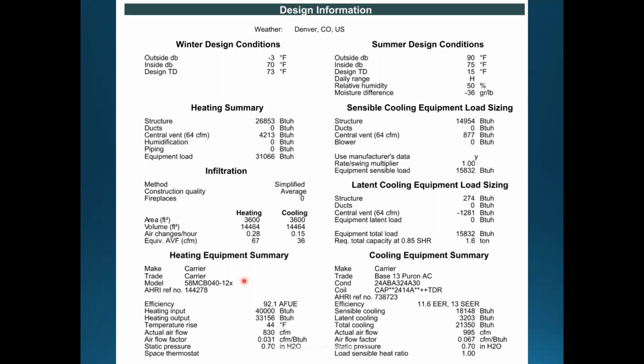If Carrier doesn't have a smaller or bigger furnace to meet the load — let's say in this case it was a 40,000 BTU furnace, but let's say Carrier didn't make a 40,000 and the smallest thing they had was a 60,000 — well, 60,000 is going to be too big, oversized technically, but the code allows that if it's the smallest thing that maker makes. We're good to go, we just move on with life.